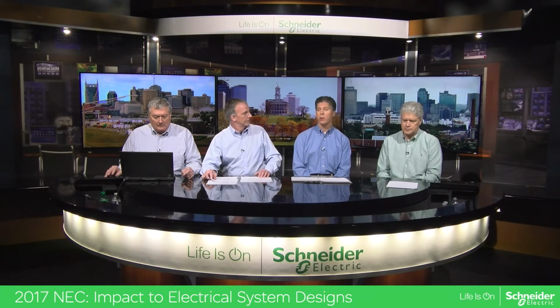This is a big change. It requires specialized test equipment, so you're going to need testing agencies. This is not the type of equipment that most electrical contractors will have available to them within their company. And I would say this will be one that the enforcement community picks up on really quick with regard to asking for the information and the documentation. That's correct. This isn't probably one that slides through for a while. I think it's one that you have to be right on top of. That's right. I'm glad you mentioned CT polarity. I think that's one of the trouble spots that we see most frequently out in the field.